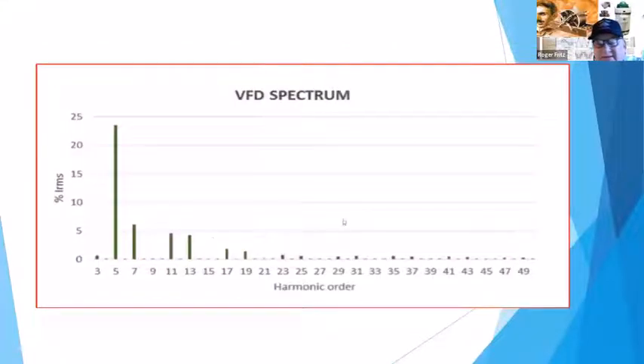So again, this looks at a spectrum order from that firing, what happens. You can see your third isn't too bad, but that fifth can be like 23, 24% of the fundamental current. So if you have 100 amps, you could also have 25 amps of this current showing up in the circuit. And then it attenuates all the way out, clear to the 49th and 50th harmonic order.